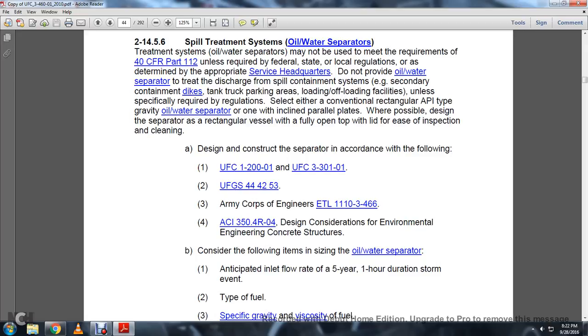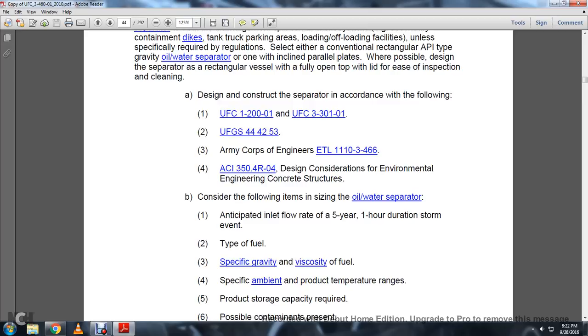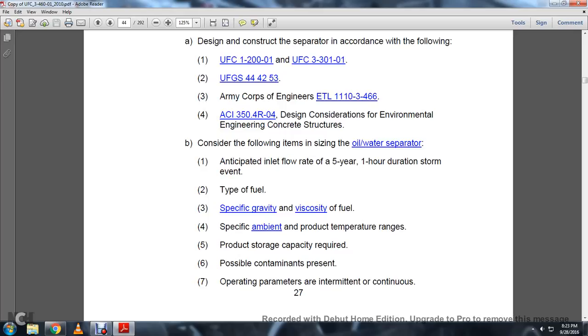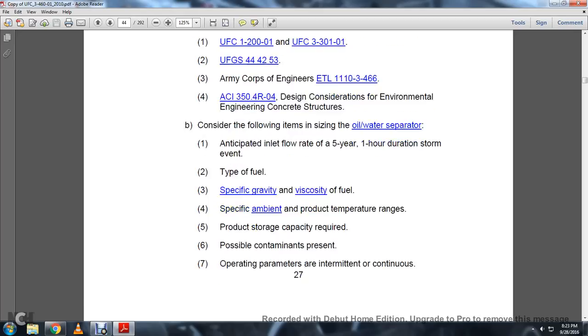Design and construction of the separator in accordance with the following: UFC 1-200-01 and UFC 3-301-01, UFGS 44 42 53, Army Corps of Engineers ETL 1110-3-466, ACI 350.4R-04, the design considerations for environmental engineering concrete structures. Consider the following items in sizing the oil water separator: anticipated inlet flow of a 5-year, 1 hour duration storm event, and typical type of fuel, specific gravity, viscosity of the fuel, specific ambient product temperature ranges, product storage capacity required, possible contamination present, and operating parameters.